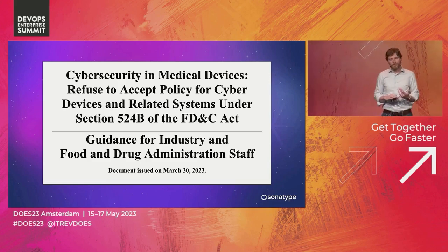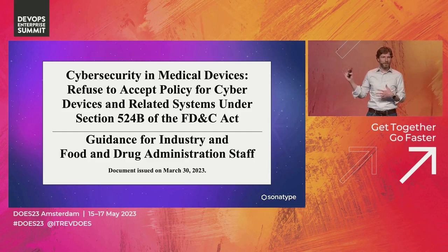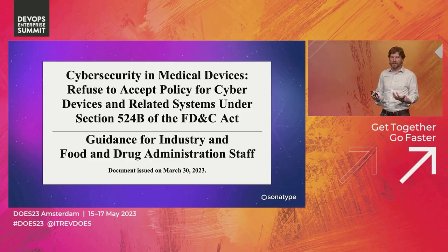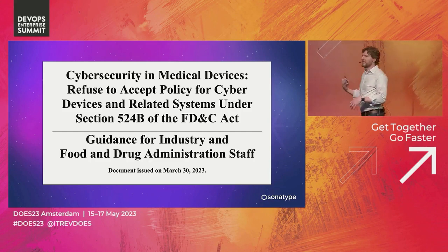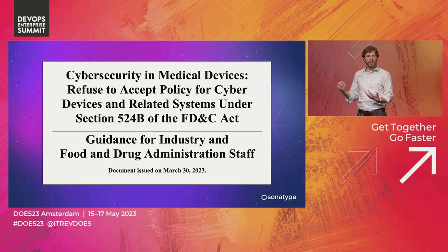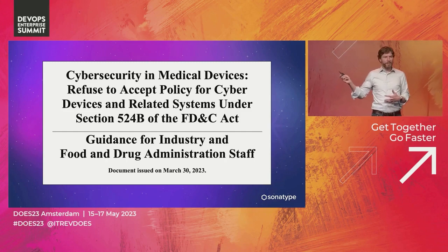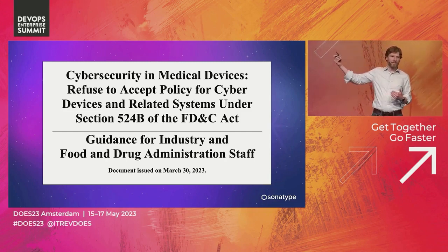They expect the manufacturers of medical devices now to be able to say what open source software is in that device, to have a system for monitoring that open source for vulnerabilities, to have a disclosure and an update procedure to respond to critical vulnerabilities. And this is in large part because these medical devices are often the entry for these hospital attacks.